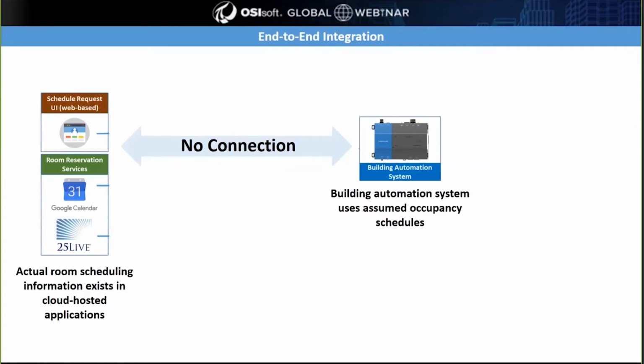The most common approach to HVAC scheduling is still to manually enter schedules within the automation system to cover standard business hours—in an office, maybe 5 a.m. to 9 p.m., Monday to Friday, with reduced hours over the weekend. In some cases you might have holidays programmed, but that's really the standard approach. The issue is that the programmed schedule is just an estimate to cover the worst case, and it doesn't account for the actual schedules of any individual space.